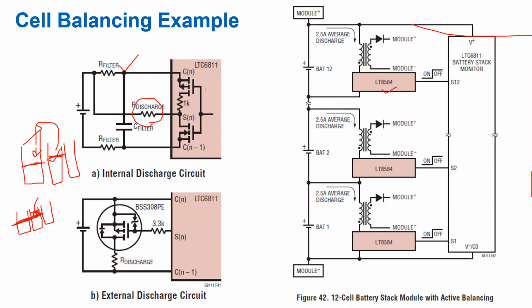If you want to increase the discharge further, generally it is not required. But if you want to increase the discharging current, you can have an external discharge circuit for that purpose. Whereas in case of active balancing, specifically for battery modules, we can have higher currents, and then we use these ferrite core transformers for this purpose, along with the LT8584 chipset, which does the job of active balancing.